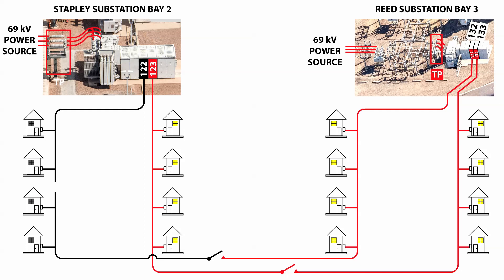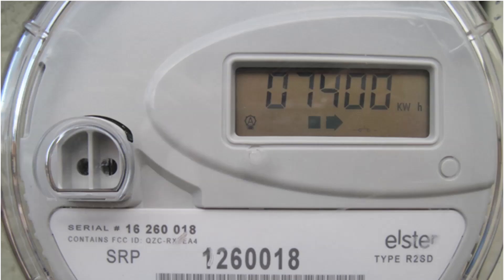Now 800 to 1,200 customers have no power at their homes, and I am called out by DOC — the Distribution Operation Center — to locate the fault and isolate it from the power system. DOC provides me information about the outage, including the location of the affected houses. Outage information is provided by digital power meters at each house, and each digital meter delivers a last gasp of information upon losing power, which automatically creates an outage map in DOC.